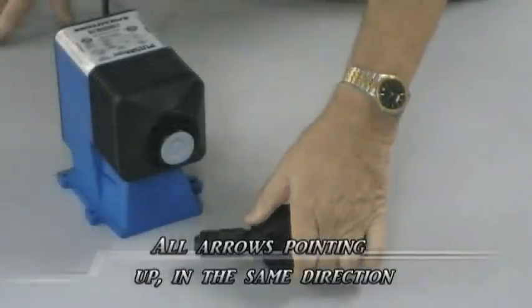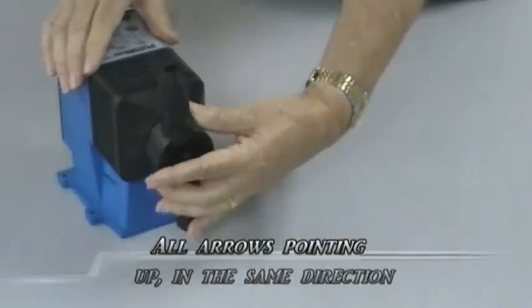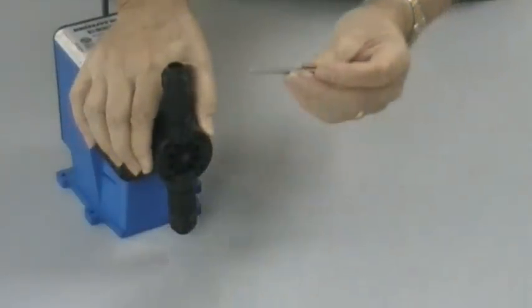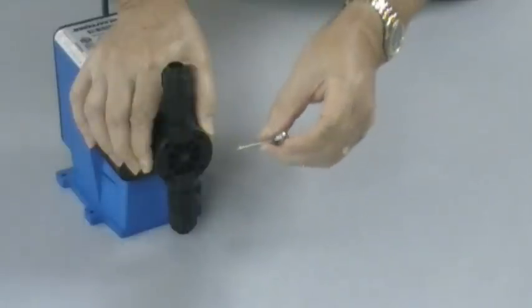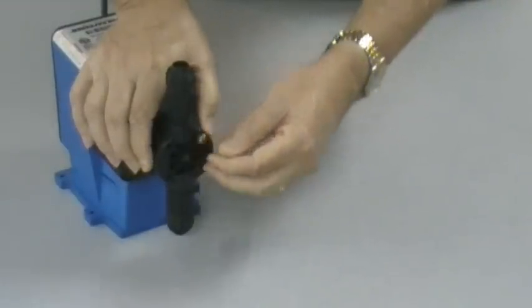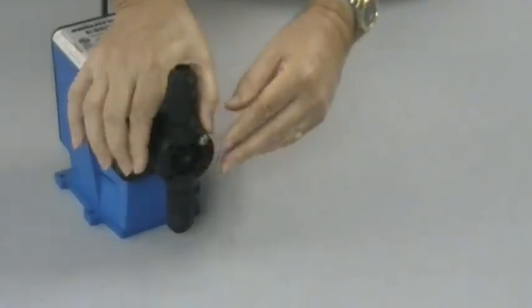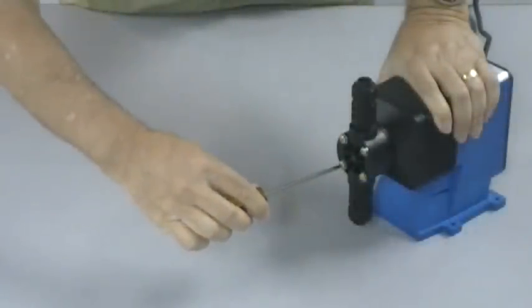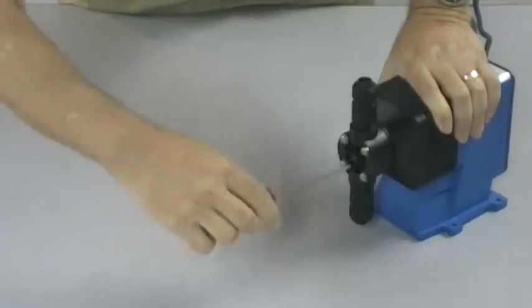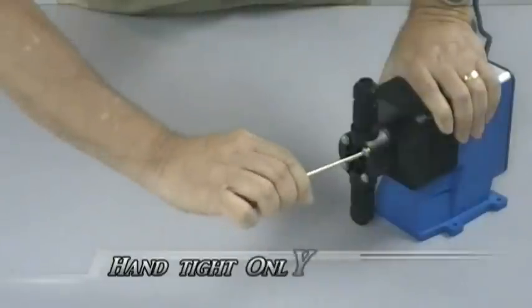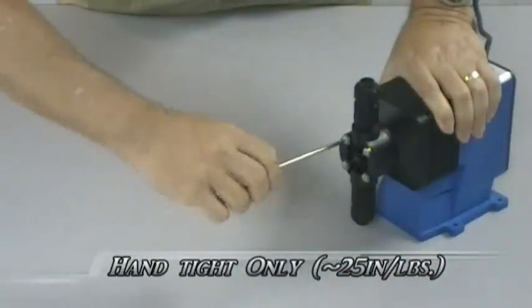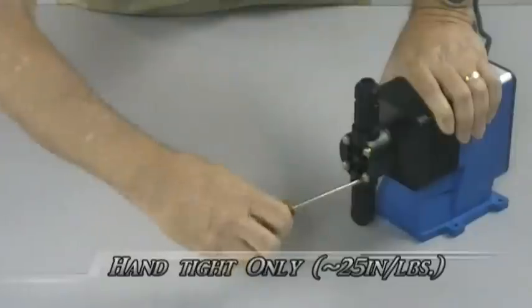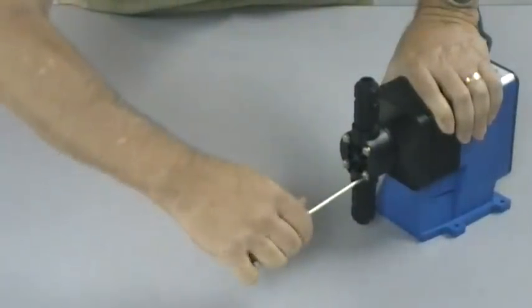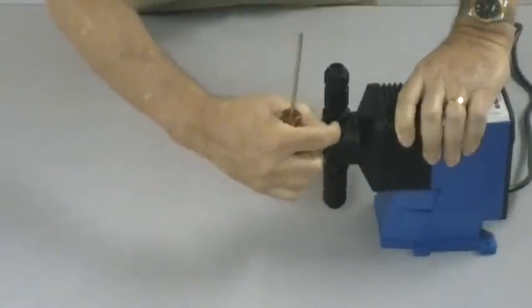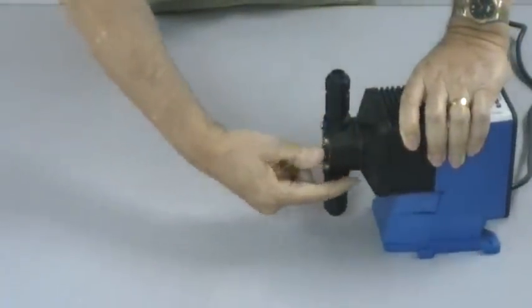Now we will install the pump head to the pump. We place the head on the pump with the arrows in the direction of flow. Take our screw, add a washer to the screw head, and insert it into the pump. Now we will finish tightening the head screws to the pump. This is done in a diagonal manner. We tighten them like this so that the gap here between the adapter plate and the pump head is even all the way around.